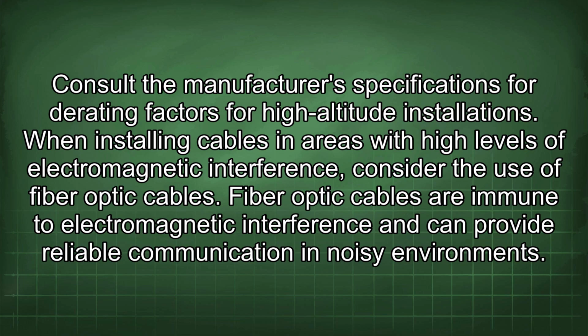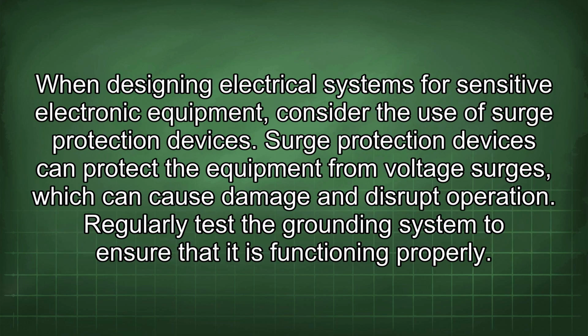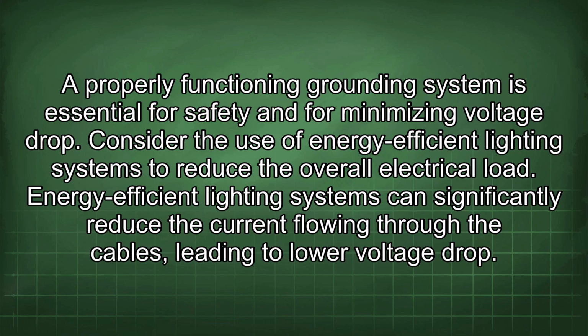When installing cables in areas with high levels of electromagnetic interference, consider the use of fiber optic cables. Fiber optic cables are immune to electromagnetic interference and can provide reliable communication in noisy environments. When designing electrical systems for sensitive electronic equipment, consider the use of surge protection devices. Surge protection devices can protect the equipment from voltage surges, which can cause damage and disrupt operation. Regularly test the grounding system to ensure that it is functioning properly. A properly functioning grounding system is essential for safety and for minimizing voltage drop.